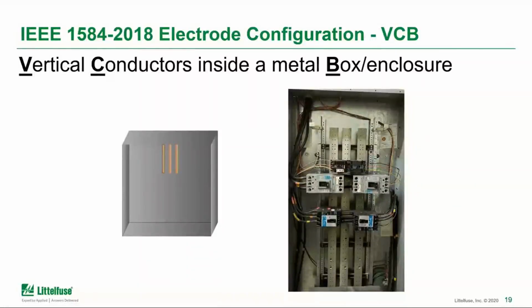Looking at the actual electrode configurations here, as I mentioned, there were several that were tested. This is the VCB, or vertical conductors in a box. You can see the photo on the right shows the conductors placed in a vertical fashion. On the left-hand side, it's not really animation, but just a quick step through. When the arc forms, the additional testing and research really showed how the arc came out of the ends of the bus bar and was directed in that way. So the arc jets that form on the ends of the bus bar really directed where that energy went. You can see how that would have an effect on the energy if you're standing in front of the panel, affecting the amount of energy coming towards you. This shows how the energy is directed down away from that bus bar in that enclosure.